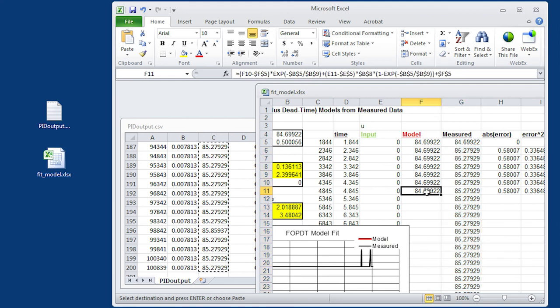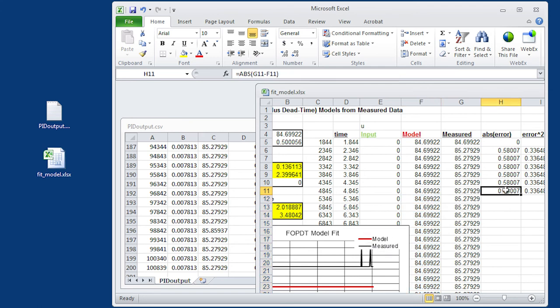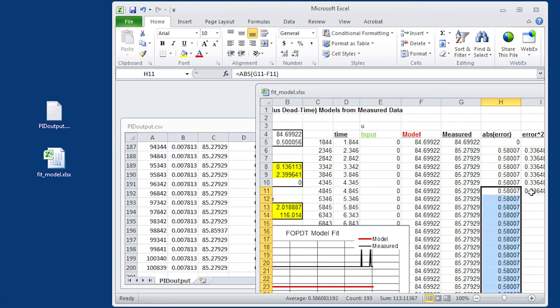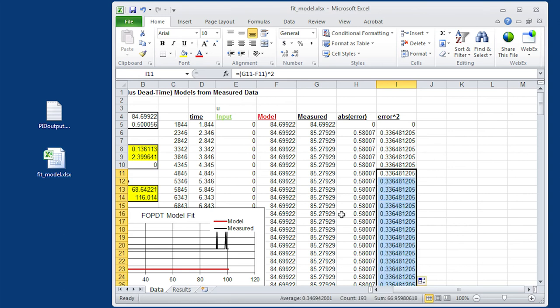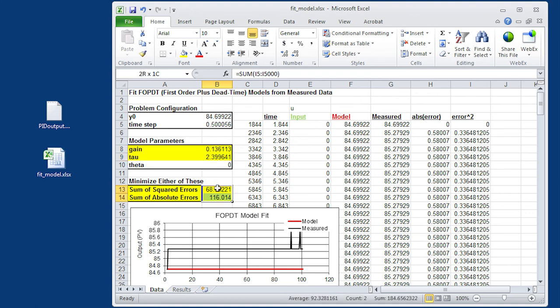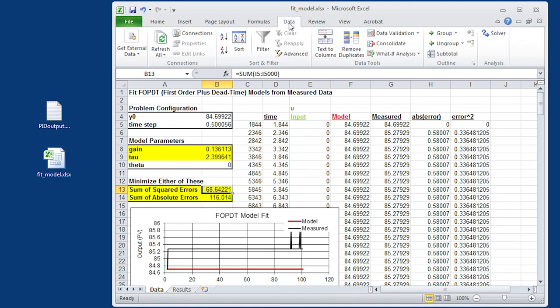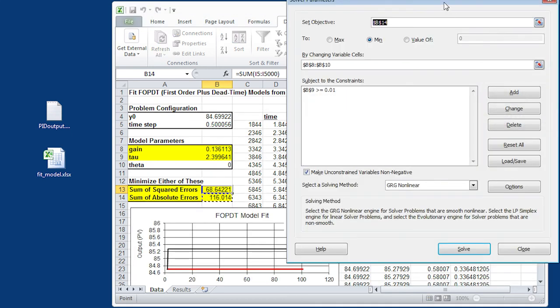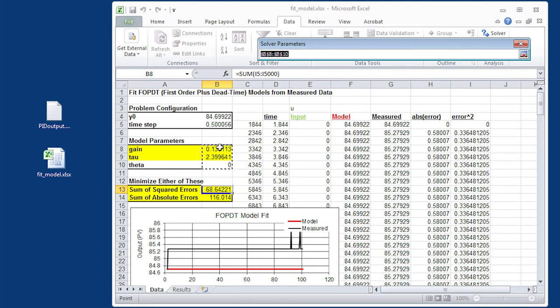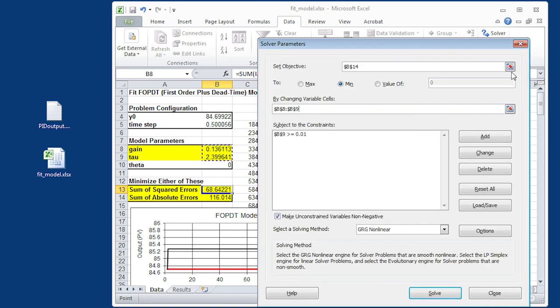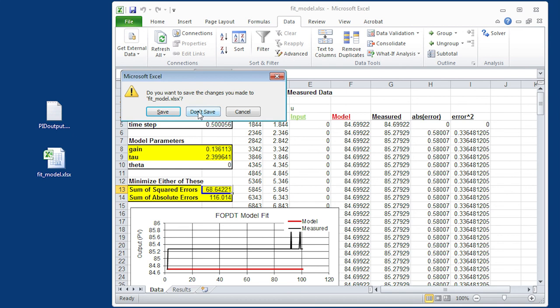And then you'll see that it has some model predicted values. And then also your absolute error and your squared error as well. Copy those down as well to sum up your errors. So now I have my gain and my time constant and I'm going to adjust those to try to fit the sum of squared errors or sum of absolute errors. And once you do that, you have your model and that is a first order plus dead time model. Now, we're not fitting the dead time there. You can optimize this with solver. So go ahead and set your objective to a minimum. You don't want to maximize, you want to minimize and then adjust your gain and your time constant to minimize either the sum of squared errors or the sum of absolute errors. And once you click solve, you'll have your model and you will be able to use that to design your controller.